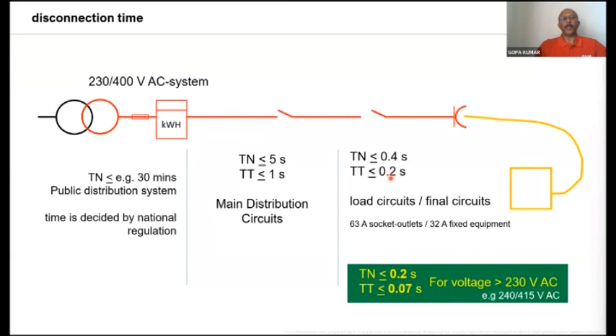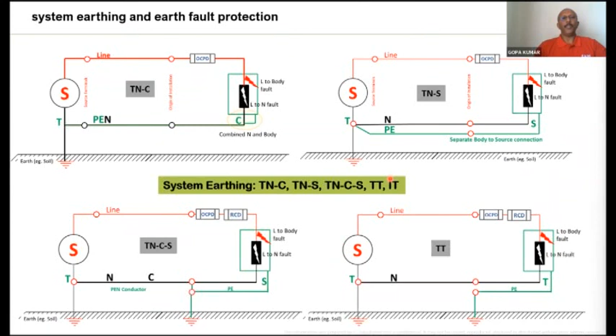That means in case of any fault in your electrical installation, in order to provide shock protection and to avoid fire, the MCB is supposed to trip within this particular time. And every electrical installation, while designing, you are supposed to take care of it. For that, the subject called system earthing plays a major role. System earthing is classified into TN-C, TN-S, TN-C-S, TT, and IT. These are very well explained in the Indian standards and the National Electrical Code.